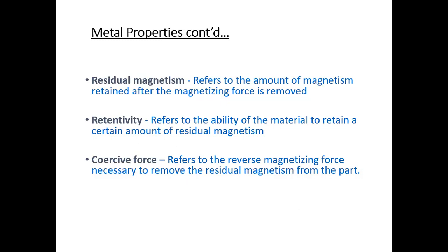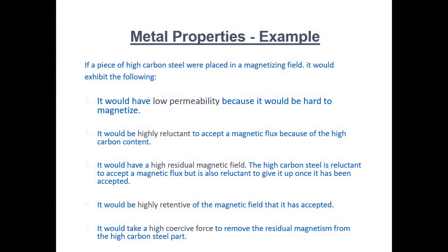Now, coercive force refers to the reverse magnetizing force necessary to remove residual magnetism from the part. If the residual field is less, then less reverse magnetizing force is required to remove the magnetic field, and that reverse magnetizing force is known as coercive force.